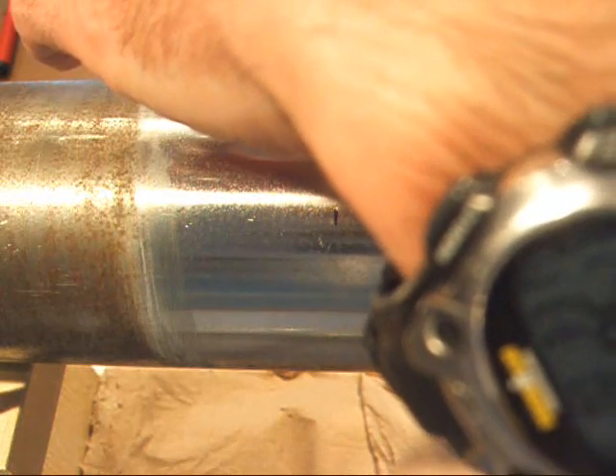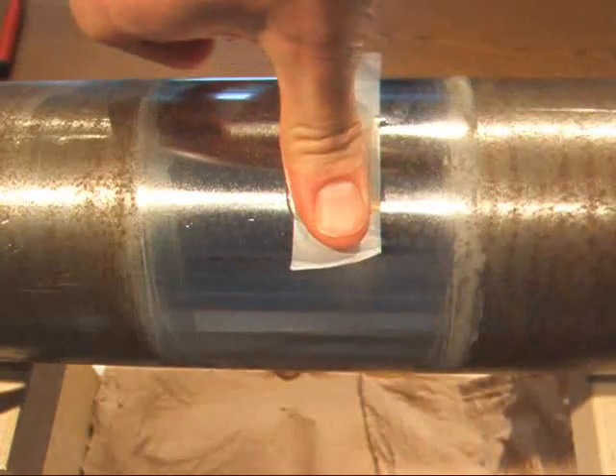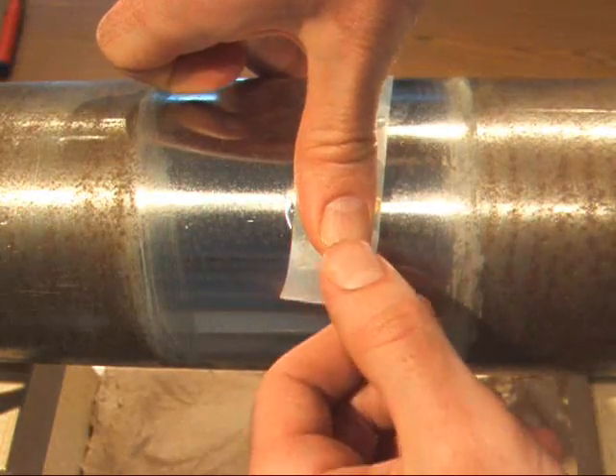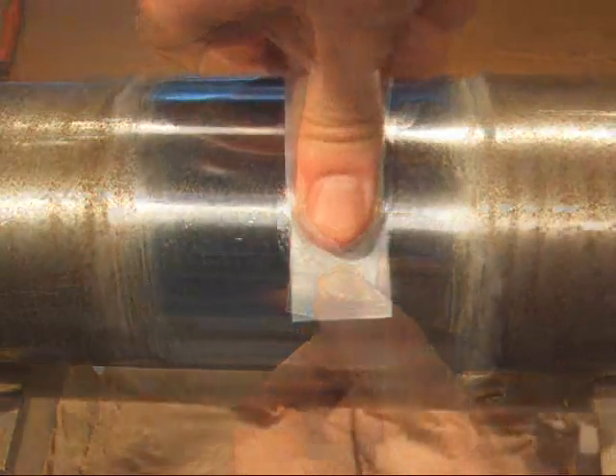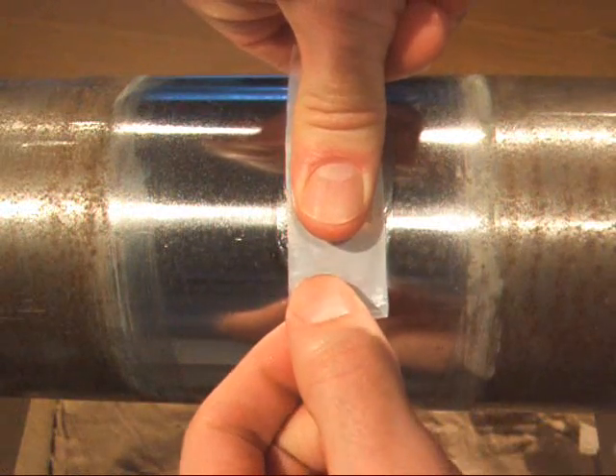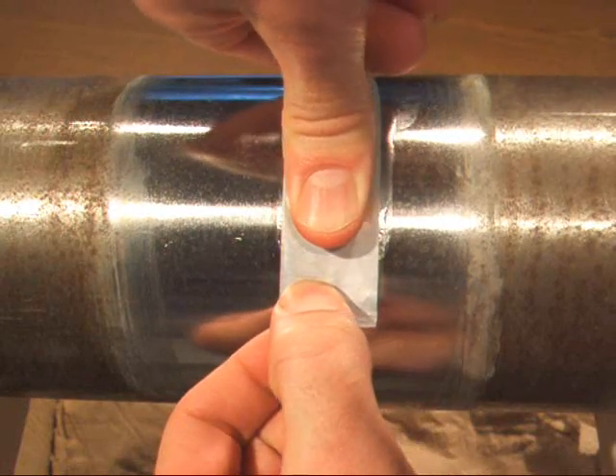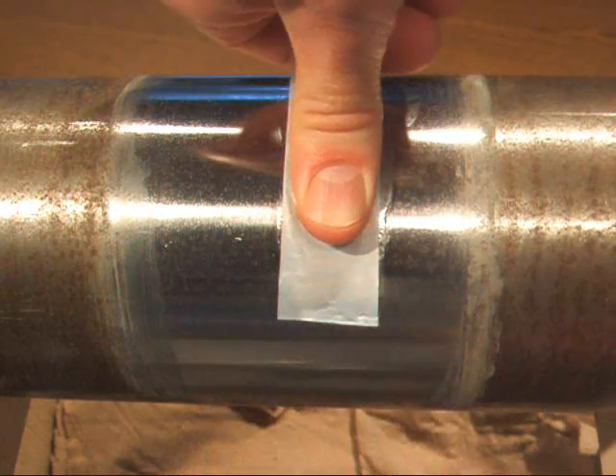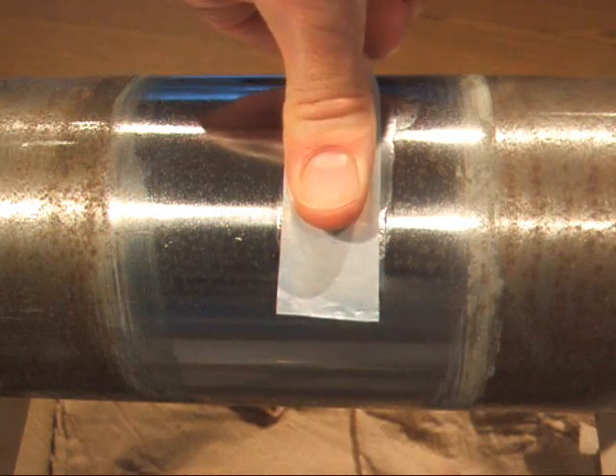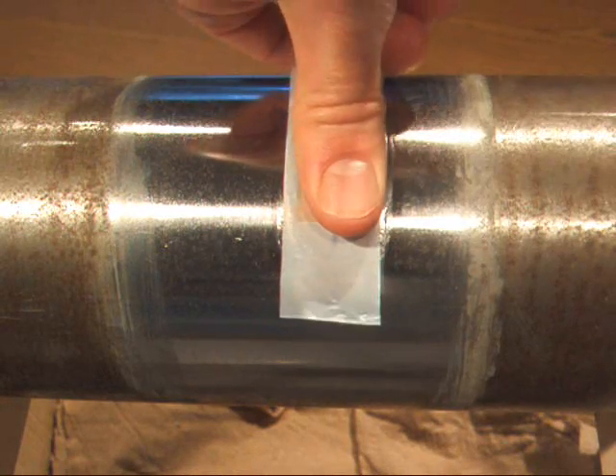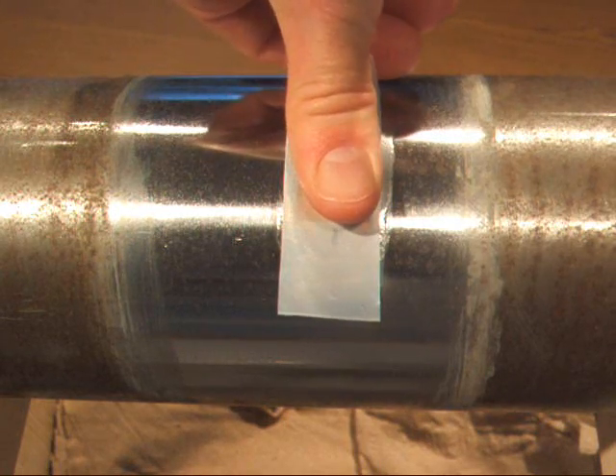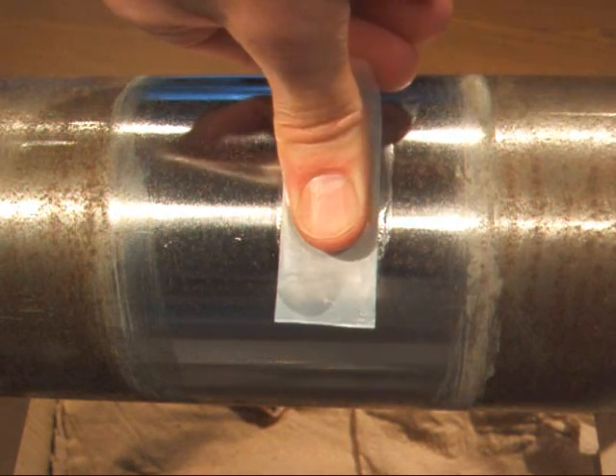I'm going to lift up the tape. And in one swiping motion, I'm going to push down with the tape. Now that we've swiped down the gauge and the glue, you want to hold pressure on the gauge and sort of roll your thumb so that you're reaching all four corners of the gauge. You want to apply pressure for at least 60 seconds.